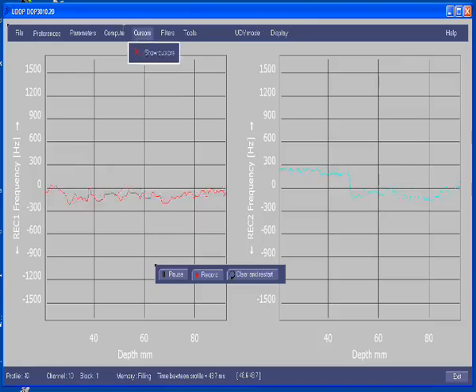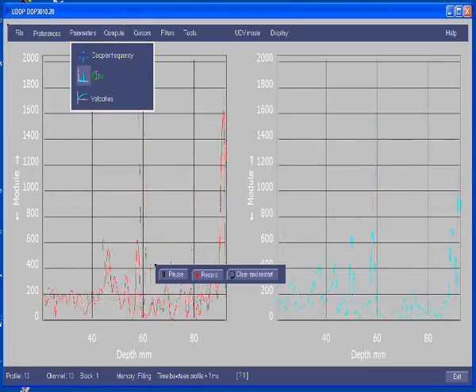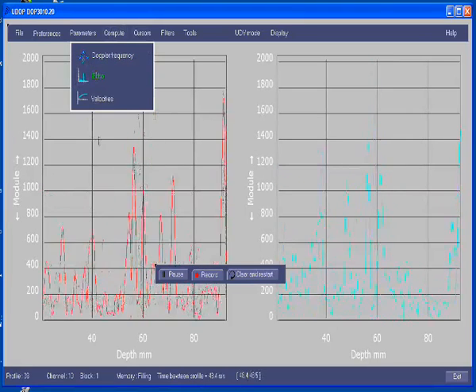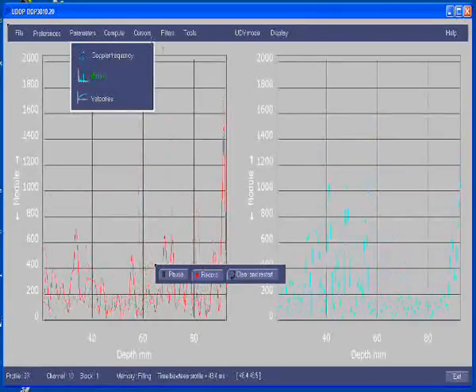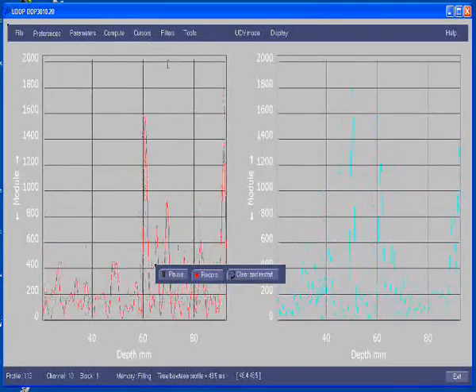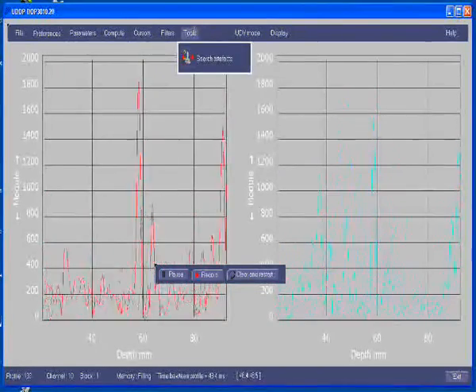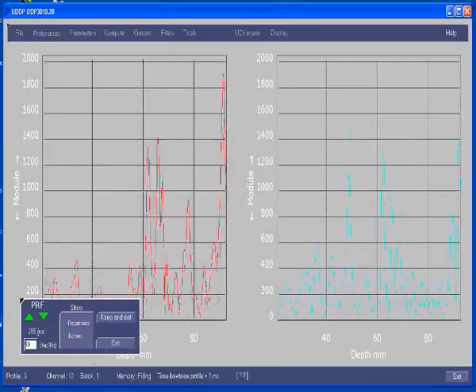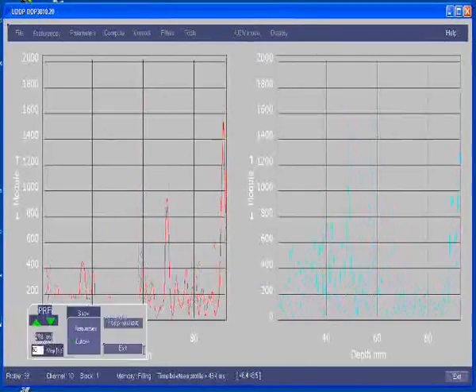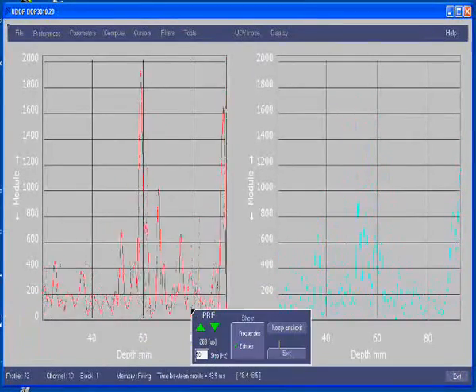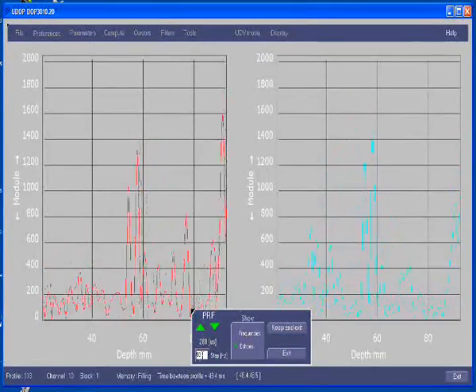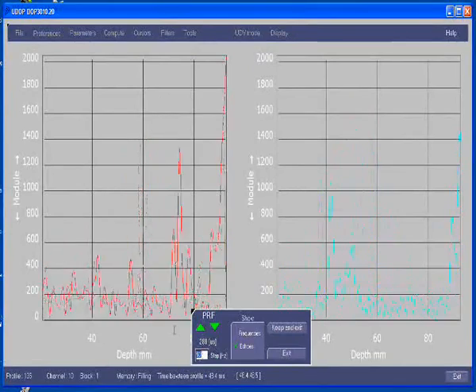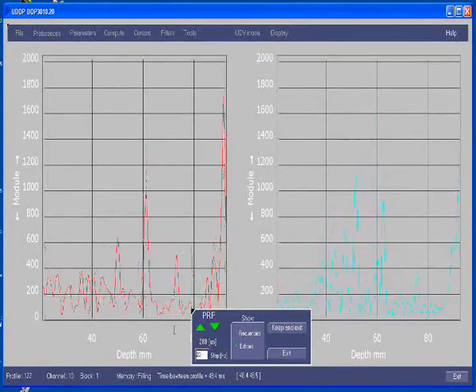Let's have a look on the echo profile. The echo profile allows us to be sure that no artifacts are present. In order to be sure of that, we will use the search artifact tool. This tool allows us to change a little bit the PRF. First, we will define the step to 20 hertz and then we will change the PRF step by step and see the influence on the echo profile.